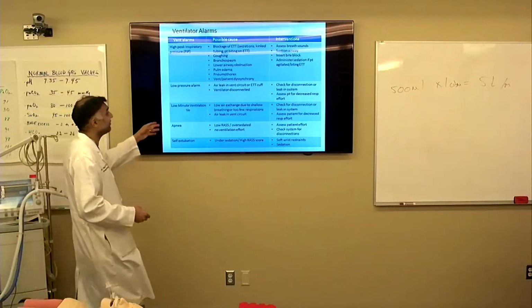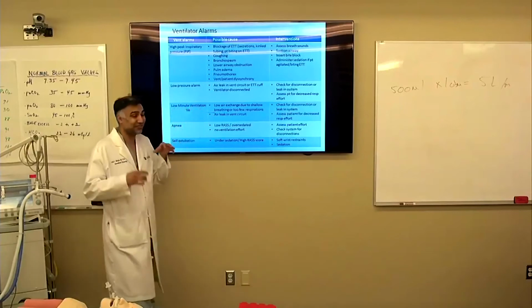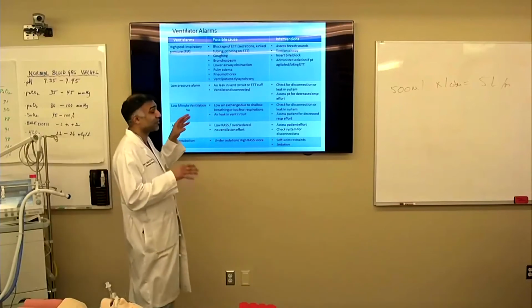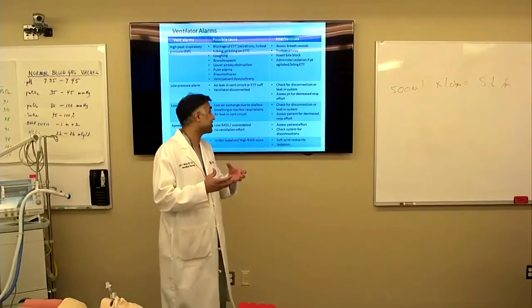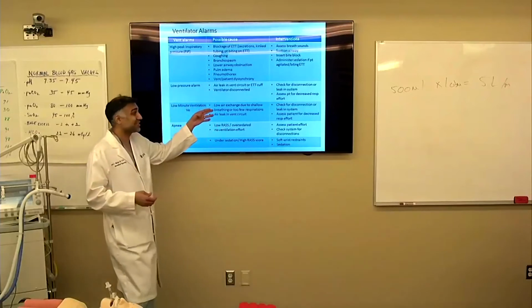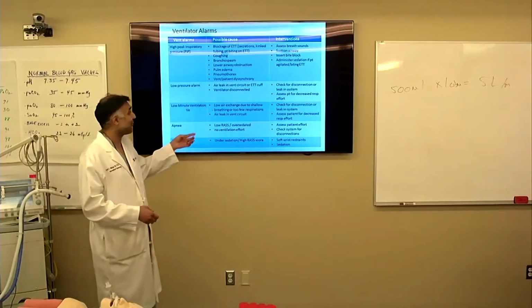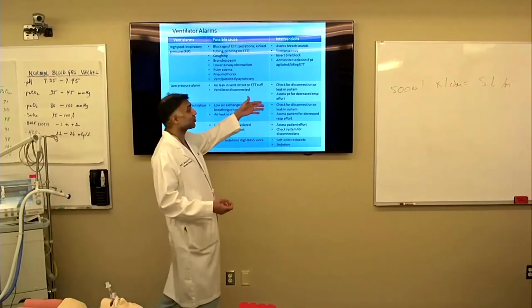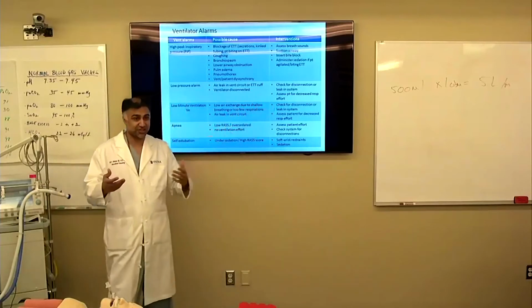When you look at low minute ventilation, it means you're not getting enough air into that patient, or the ventilatory rate or volume is too low. You can see this with shallow respirations, or again, there's a leak in the circuit. It almost always comes down to you having to check your circuit in those situations.